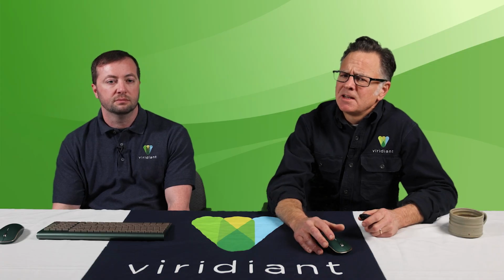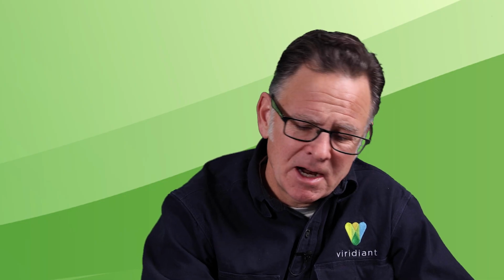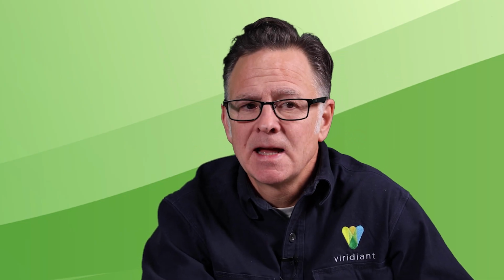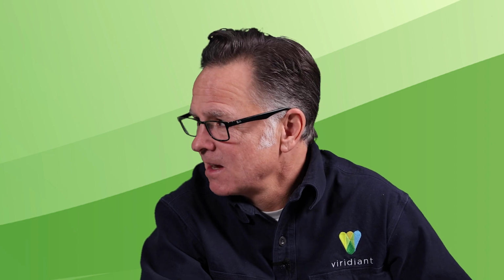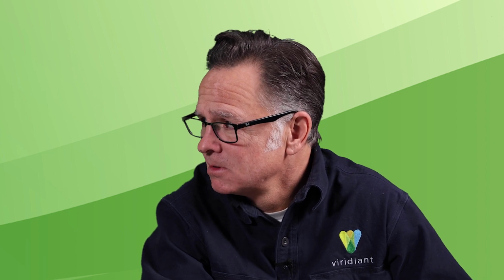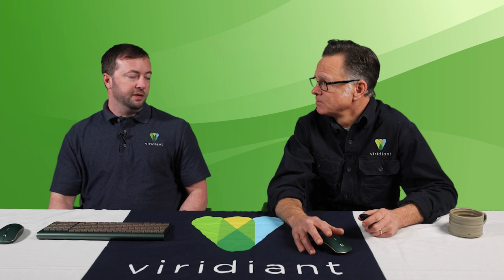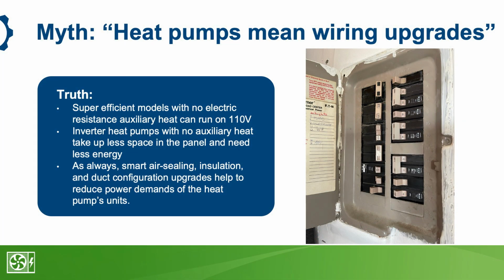I've also heard that if you have an older house and you want to switch to a heat pump, you're going to always have to have wiring upgrades. Do you think that's true? In some cases it will be true, but there's many cases where it won't be true. There will be some houses where that's necessary, but there will also be a lot of houses where you can use the existing panel. In the panel that you see on the slide here, that house switched from an oil boiler that was providing heat and domestic hot water to an inverter cold climate heat pump and an electric water heater. And they were able to do that without any panel upgrade.